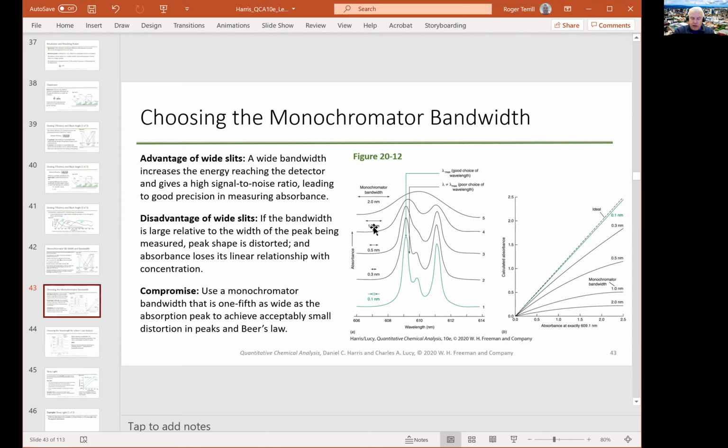And that's because of spatial filtering. As you change the cone of angles that the monochromator can accept from the source, you greatly decrease the amount of light that can get into the spectrometer. You increase the purity, but you decrease the number of photons. So anyway, I'm sure there's ways around this, but for visible light, it's a tricky proposition, and you just use a bright source, etc., and you can get around it.